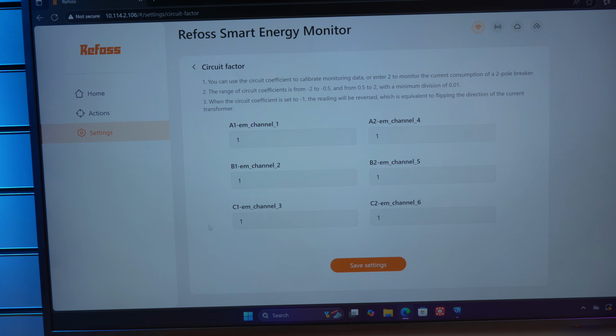This wording doesn't really make much sense to me, but what I suspect this is talking about is, in the US with a split phase supply, this device will be measuring the voltage between each phase and neutral, which would be 120 volts. Whereas if you had a 240 volt device that's connected across the phases and a CT around one of those wires, you'd set this to 2, which would double the measured power to compensate for only measuring half of the voltage. I think. Don't quote me on that.